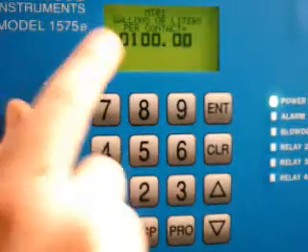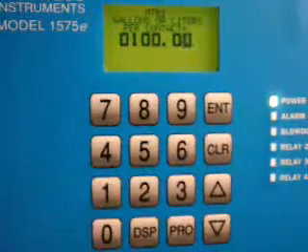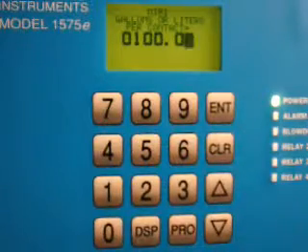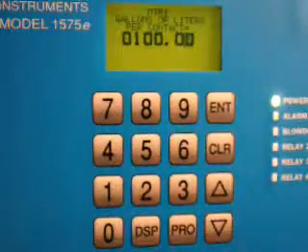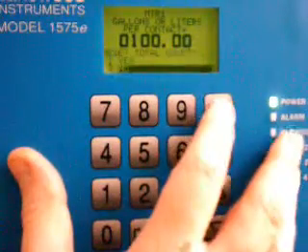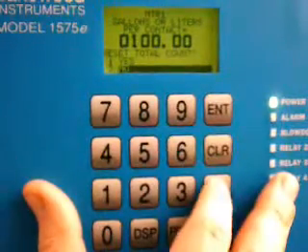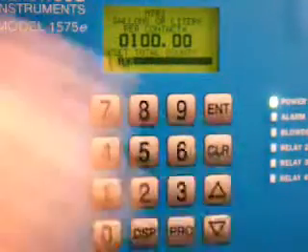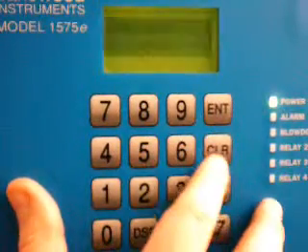You have to look at the water meter, understand what your manufacturer sent you. The default is 100 gallons per contact. It could be 1,000 gallons per contact. It could be 10 gallons per contact. You have to clarify that with your water meter. So in this instance, if it was 100 gallons, I just go ahead and hit enter. I could reset the totaling function, which totals water meter so it shows you how much gallons you've actually processed through the controller. And I'm going to say yes, go ahead and reset that. I get a reset screen. I hit clear.